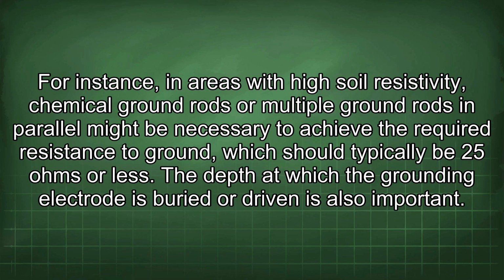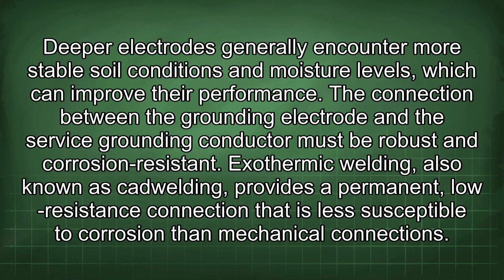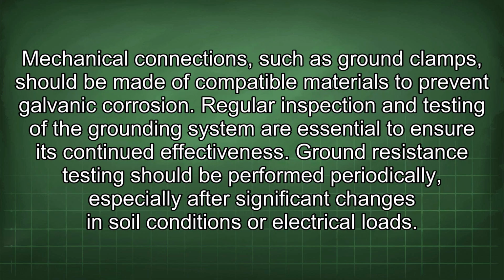The depth at which the grounding electrode is buried or driven is also important. Deeper electrodes generally encounter more stable soil conditions and moisture levels, which can improve their performance. The connection between the grounding electrode and the service grounding conductor must be robust and corrosion resistant. Exothermic welding, also known as cadwelding, provides a permanent, low-resistance connection that is less susceptible to corrosion than mechanical connections. Mechanical connections, such as ground clamps, should be made of compatible materials to prevent galvanic corrosion.